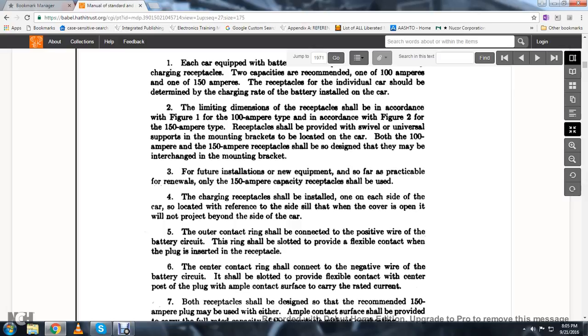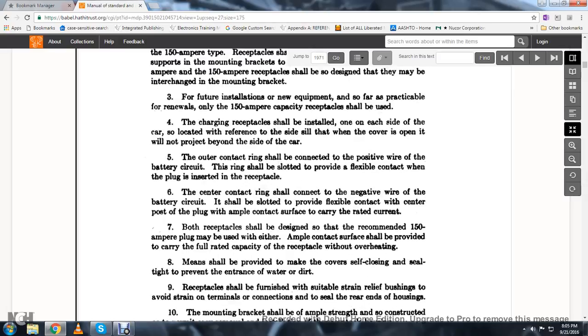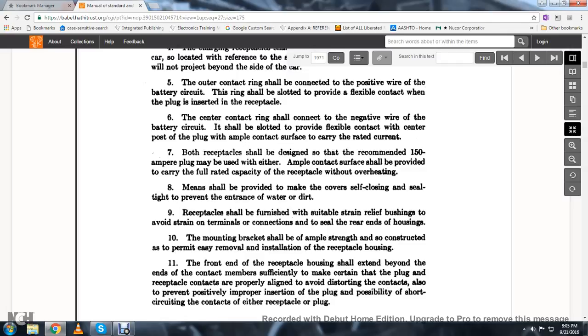The outer contact ring should be connected to the positive wire of the battery circuit. The ring should be slotted to provide flexible contact with the plug when inserted. The center contact ring shall be connected to the negative wire of the battery circuit, slotted to provide flexible contact with the center post of the plug, with ample contact surface to carry the rated current capacity. Receptacles should be designed for a recommended 150 amperes with ample contact surface to carry full capacity without overheating.